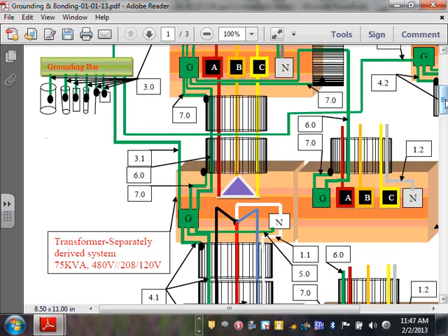So you can take a 3/0 from here, go all the way down to transformer tap feed 1, transformer 2, transformer 3, transformer 4, and go from one closet to closet. Also commonly done. Any comments, any questions, guys, about this? A lot of your data and telephone companies like to see that master ground bar on the outside of the phone, and they give some access to it for their grounding purposes rather than trying to tie on to a piece of conduit. And you're absolutely right.